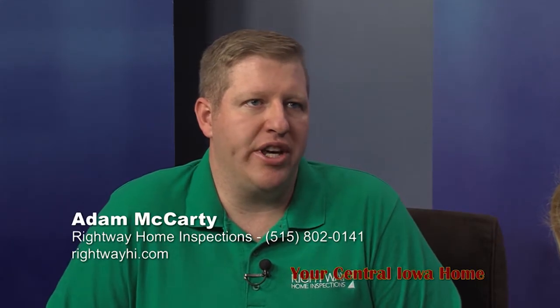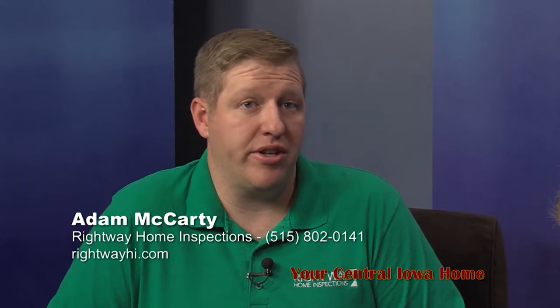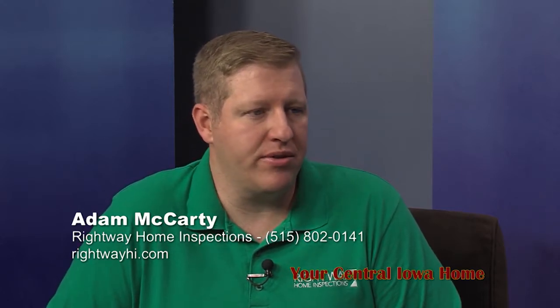So when you go into the basement, looking at the electrical panel, are there certain things you're looking for there? Yeah, the biggest things, especially if it's an old house, are some of the panels. There are panels that are proven fire hazards, such as Federal Pacific panel. Also, I'm looking for aluminum wiring in some older houses. That again is another fire hazard if it's present in a house. It can be fixed fairly easily, but it's definitely something you want to watch out for.